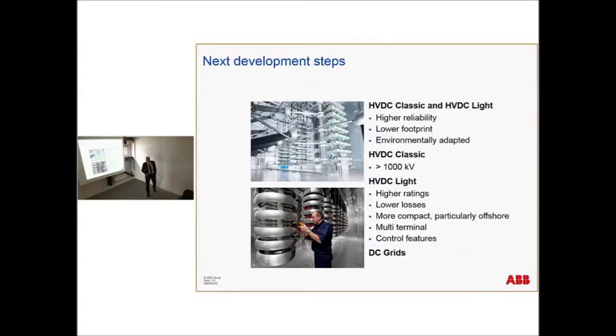With the DC breaker. What's the highest voltage on the cable? Today, the highest voltage is on the cable that I circulated, 320 kV if you're using extruded cable with plastic insulation. But you can use also the mass impregnated cable for HVDC light applications. And that is the case for this link, Skagerrak 4 between Norway and Denmark. They were using what we call mass impregnated cable for 500 kV, but we're using the VSC technology.